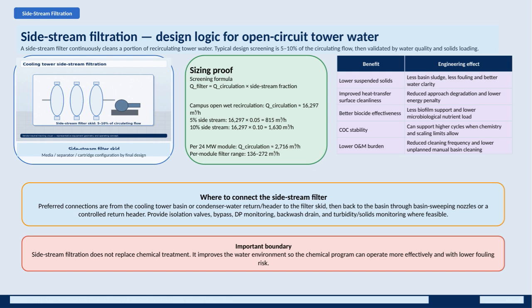The filter skid can be configured using media, separators, or cartridges depending on the final design requirements. Sizing is straightforward but essential. For example, with a campus open wet recirculation flow of around 16,300 cubic meters per hour, a 5% side stream filter handles about 815 cubic meters per hour, while 10% filters about 1,630 cubic meters per hour. For a 24 megawatt module with a circulation flow of roughly 2,700 cubic meters per hour, the filter flow range falls between 136 to 272 cubic meters per hour.